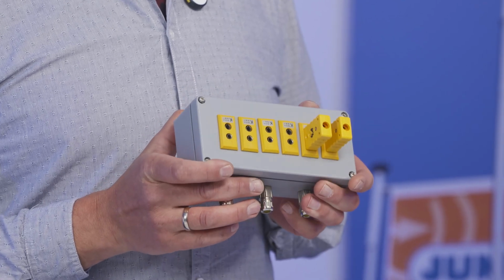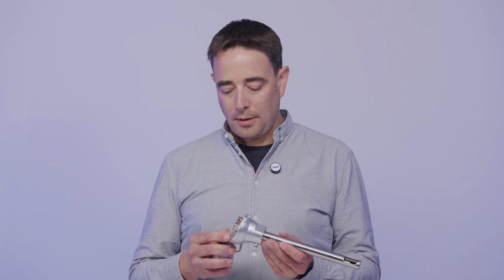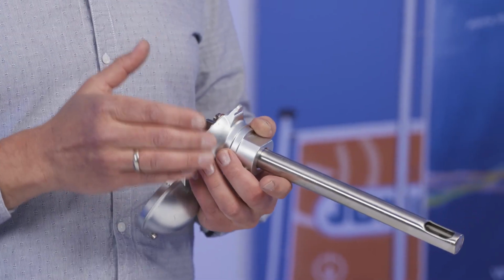Okay. Do you have three more tips for our listeners, maybe from your practical testing and calibration experience? Yeah, tip 1 is to use thermoboxes for the instrumentation tests. It's easier for the controller to do the tests. The next tip, tip 2, is to use temperature sensors with a SAT hole integrated, so the controller always has the same position during the continuous tests. And tip 3 is for the TUS measurement. It's very important to have the right position to place the TUS thermoprobes for the measurement.